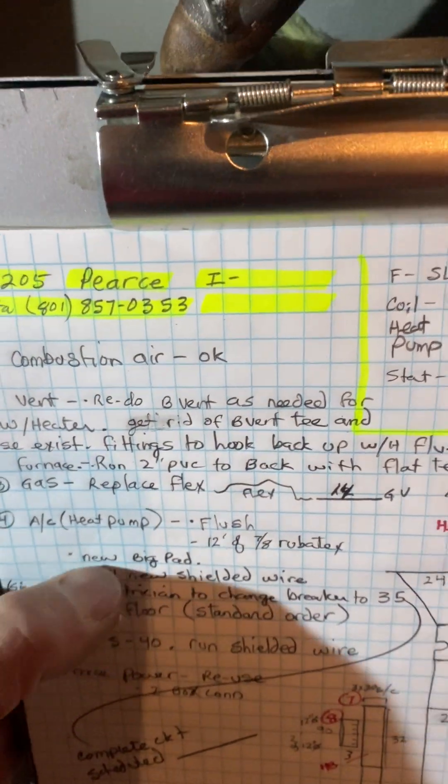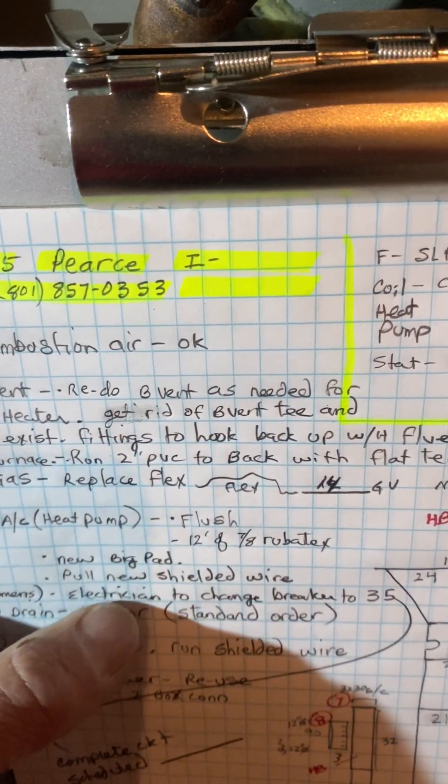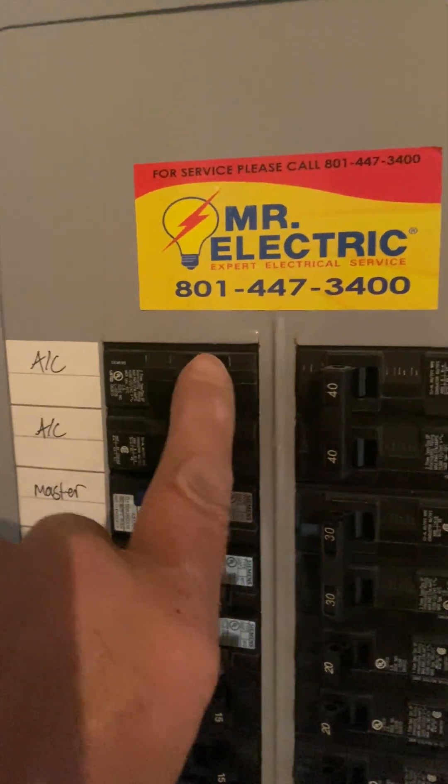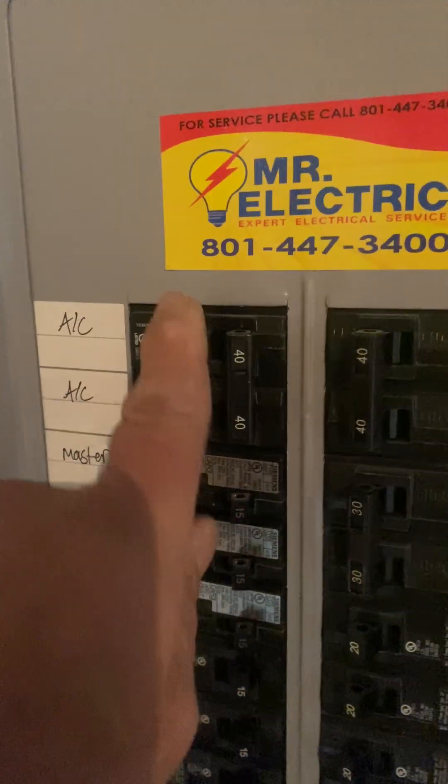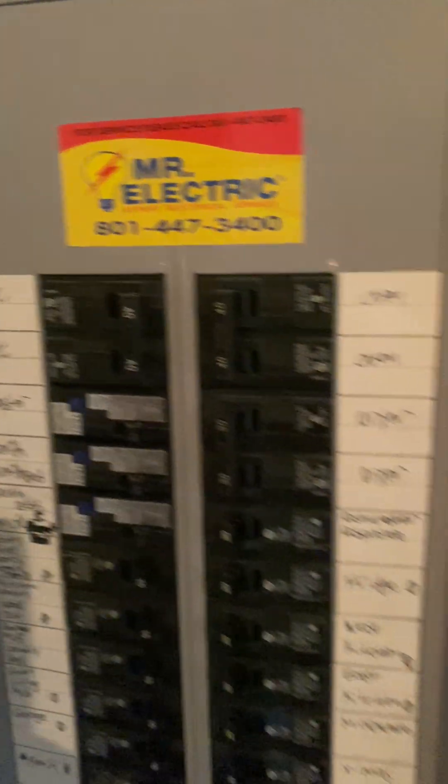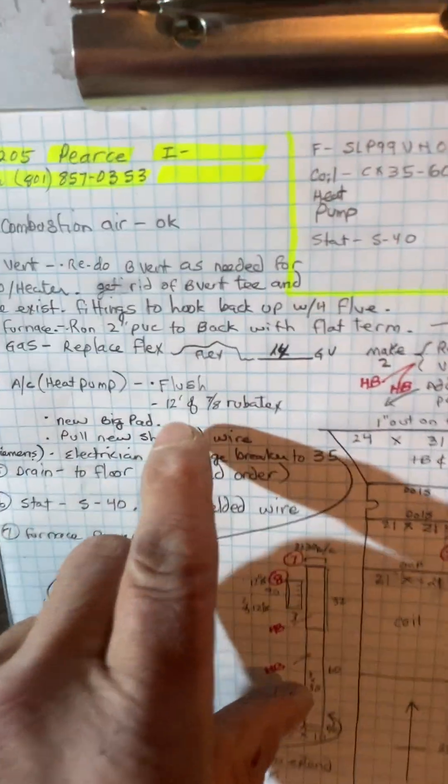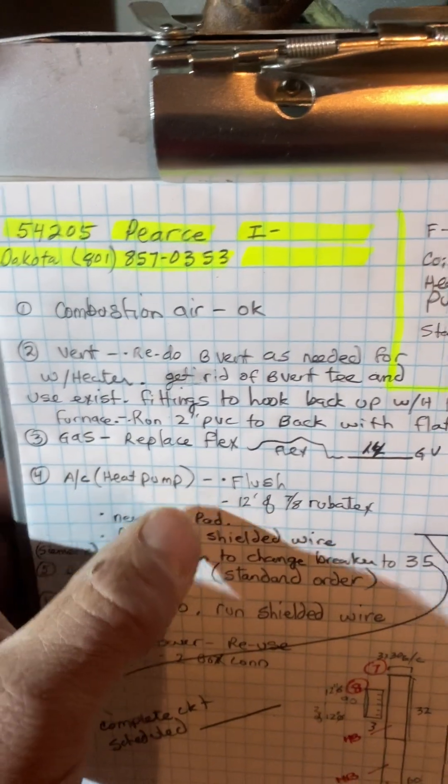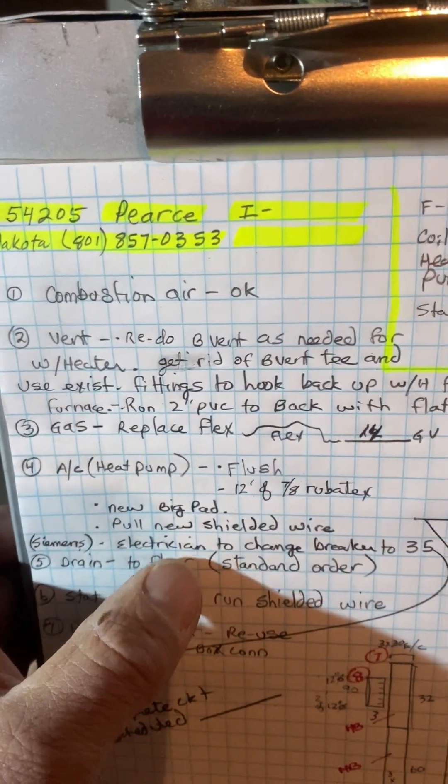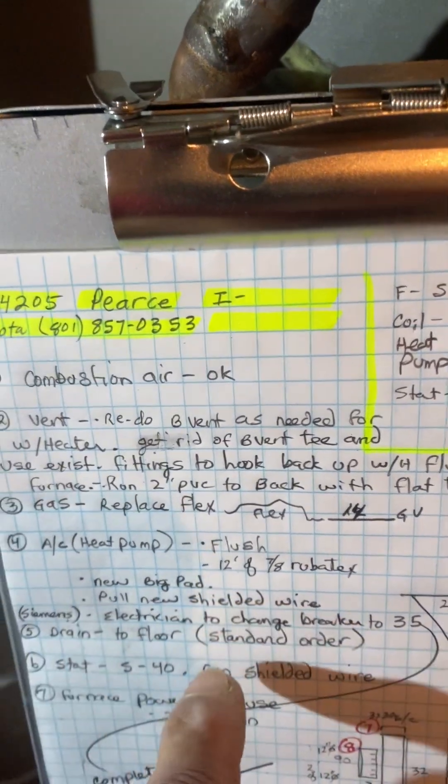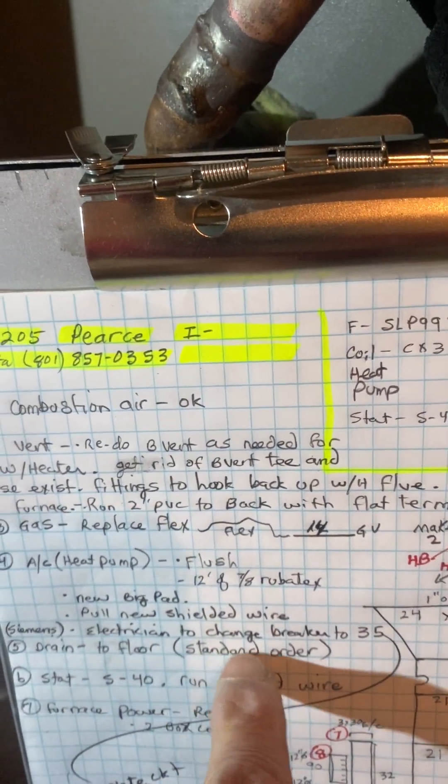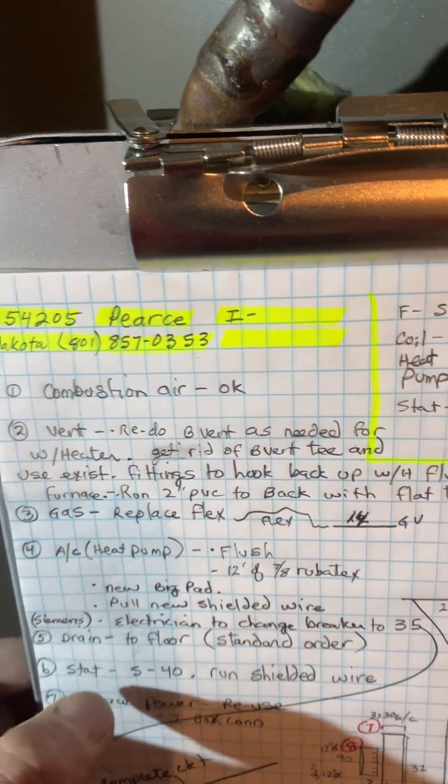Pull new shielded wire. Our breaker is a 40 amp Siemens, needs to be changed to a 35 amp, so it's an electrician to do that. Pull stranded, sorry, pull a shielded wire here, here, and to this stat.